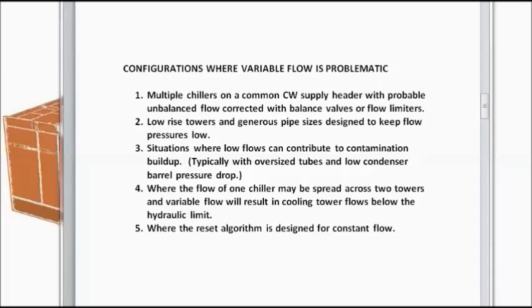This typically might happen when you have chillers which are designed with oversized tubes and low condenser barrel pressure drops. And number four, where the design allows the flow of one chiller to be spread across two towers to increase tower efficiency. Here, low variable flow could result in cooling tower flows below the hydraulic limit.